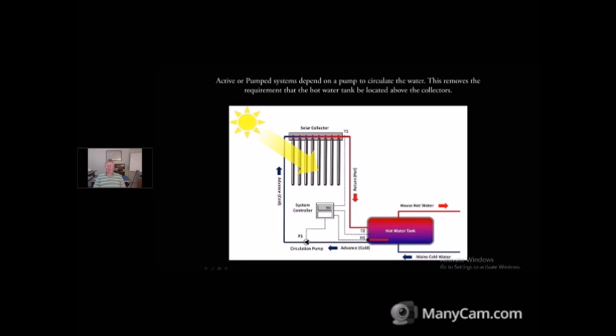This allows you to put the water tank down in a more insulated space, and that is going to be increasingly important the colder you go. As you start moving into colder and colder environments, passive systems become increasingly difficult until you get cold enough, then passive is just about impossible to make work reliably and you're into an active system.